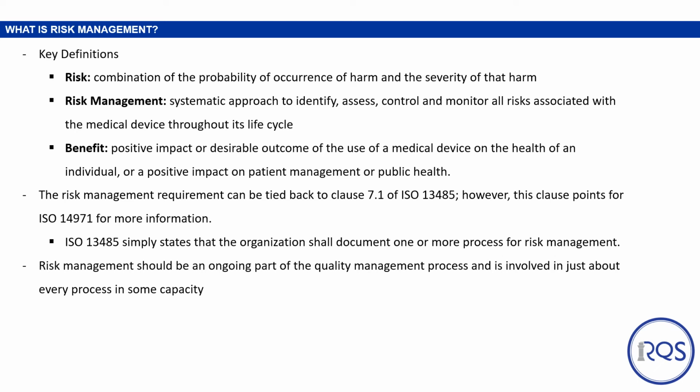Let's start out with some key definitions. A risk is the combination of the probability of occurrence of a harm and the severity of that harm. Risk management is the systematic approach to identify, assess, control, and monitor all risks associated with the medical device. A benefit is a positive impact or desirable outcome from the use of a medical device or a positive impact on patient management or public health.